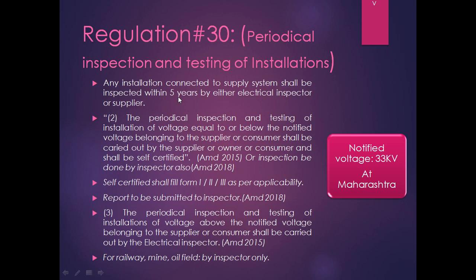Now, it says that the inspection frequency shall not be more than once in 5 years. So, within 5 years you have to inspect your installation. Now, the question is who will do the inspection? There are two options for an installation whose maximum voltage is below the notified voltage of your state. If your maximum voltage level is below the notified voltage, you can self inspect your installation, fill Form 1, 2 or 3 which is attached with the CEA regulation 2010 on measures relating to safety and electric supply. You can fill this form and submit it to the electrical inspector, or else you can call the inspector for inspection.